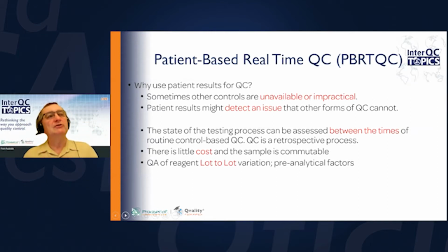On most analyzers in most laboratories these days, on the high volume clinical chemistry assays, you might put a QC material, a QC standard in once a shift, once every 8 hours or maybe once a day. And in between those quality control samples, there may be hundreds of patient samples.